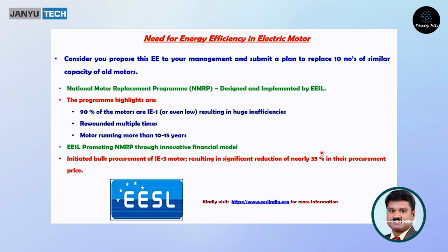But apart from that, there is a plan available by EESL. EESL is Energy Efficiency Services Limited. It's a central government company, where there is a program called the National Motor Replacement Program. This program is mainly used for replacing old motors, rewound motors running more than 10 to 15 years, very old motors, with an IE3 motor, and they assure a financial takeover of 35%. Out of 1 lakh, they will buy the motor at a reduced cost from the direct OEM and give it to you at a 35% reduction.